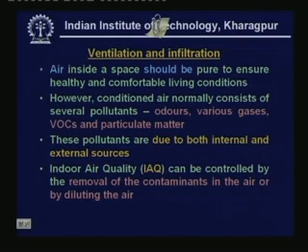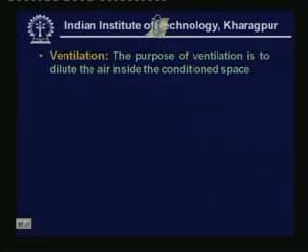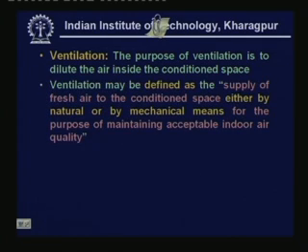Ventilation is defined as the supply of fresh air to the conditioned space, either by natural or mechanical means, for the purpose of maintaining acceptable indoor air quality. Ventilation air can comprise fresh outdoor air and some amount of recirculated air that is treated. Only about 0.2 liter per second per person is required for breathing, but the actual requirement is larger because ventilation must also dilute odors, maintain CO₂ at satisfactory levels, and pressurize escape routes in the event of fire.